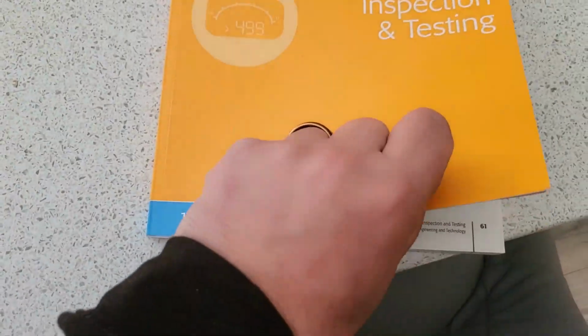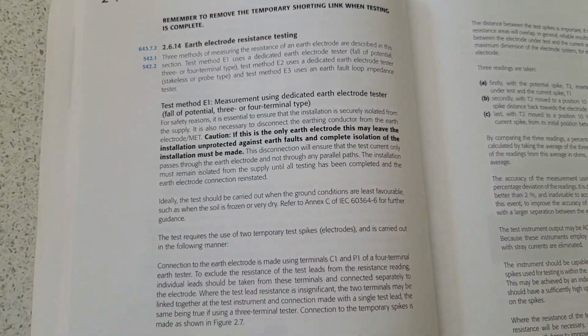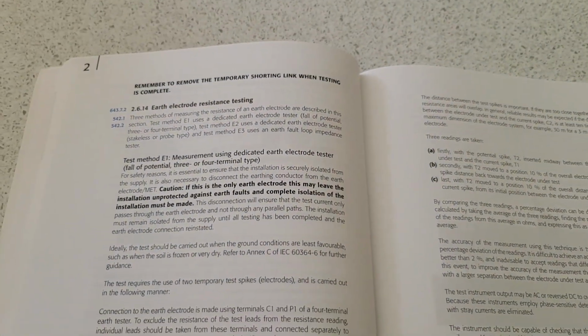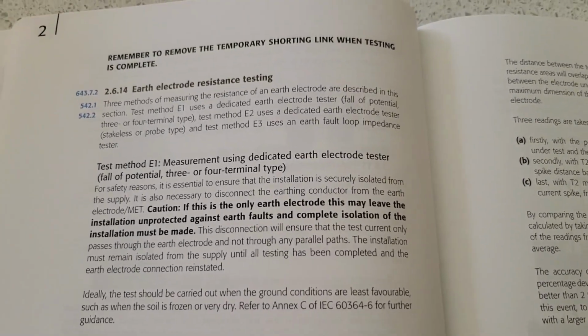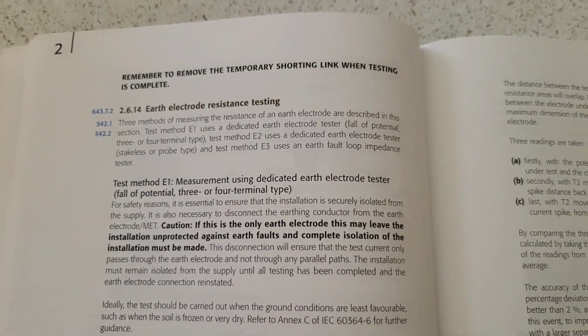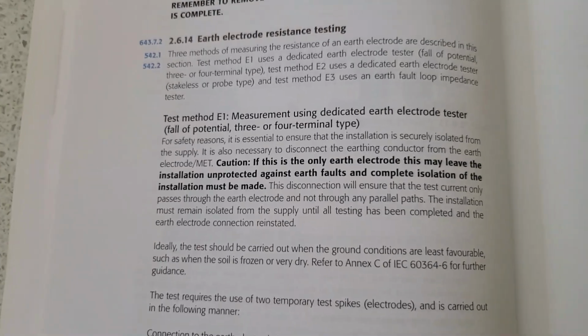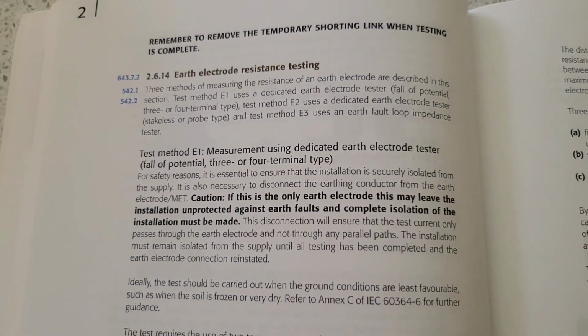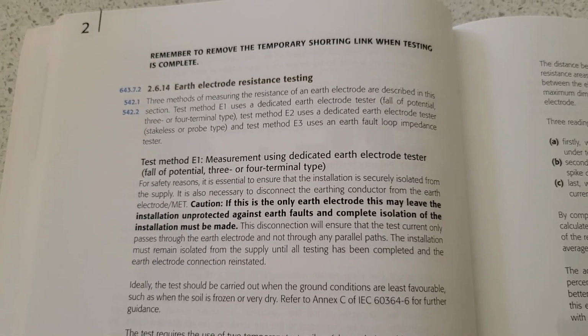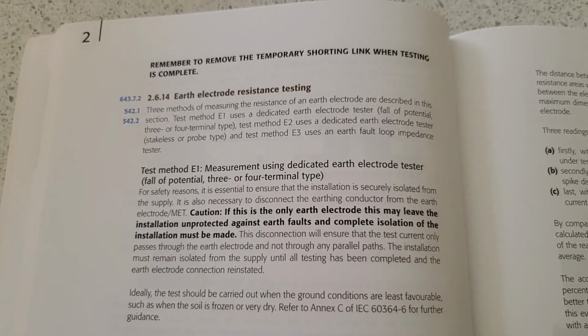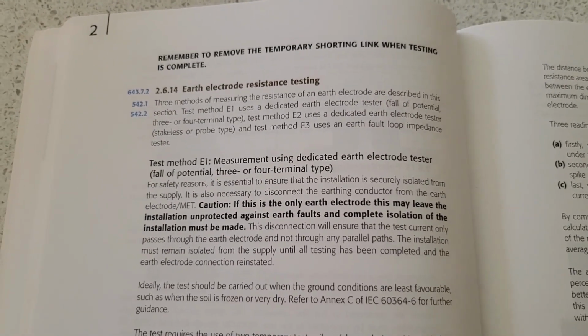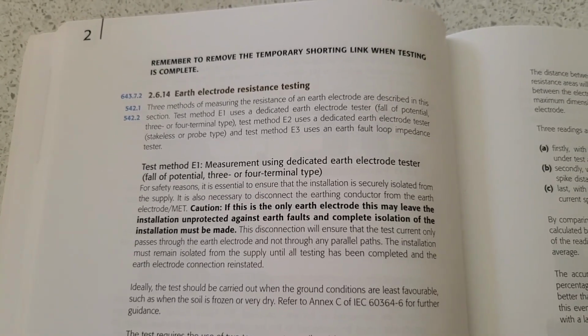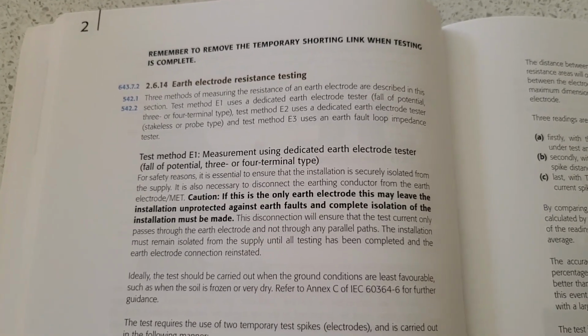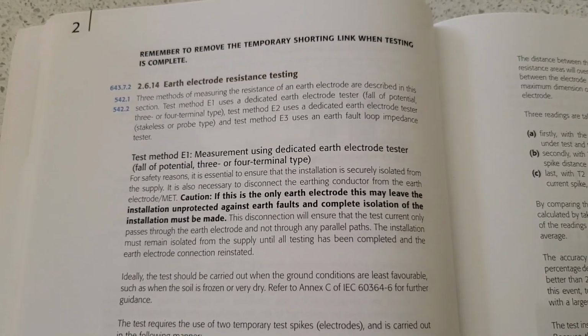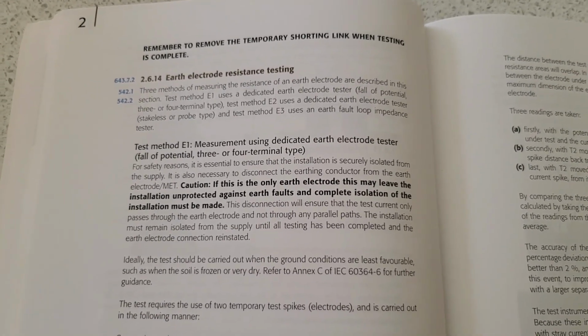Okay, so we're going to get a last bit of value from Guidance Note 3 Blue Edition. Obviously when this drops as a video release, we'll all be on the brown book by then. But I just thought we'd have a quick look through this one, and you can see here this is chapter 2, GN3, and it's talking about earth electrode testing and how there's the 3 methods. So you've basically got your earth electrode tester, which is the fall of potential for your 3 and 4 terminal types. And you can also do the stakeless or probe type measurement, and then you've got your earth fault loop impedance test, and I've shown that on this video as well.